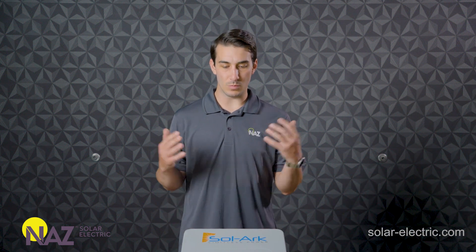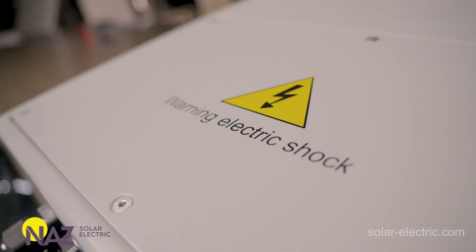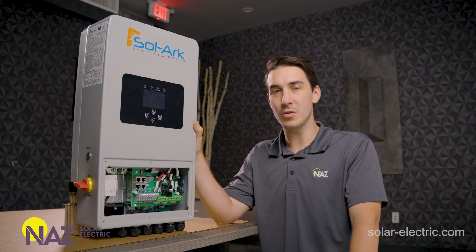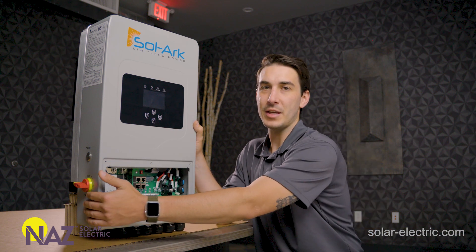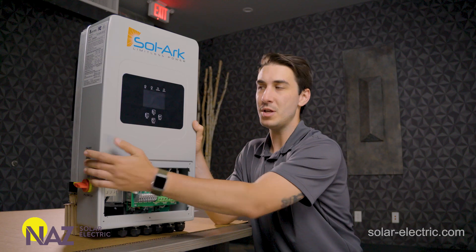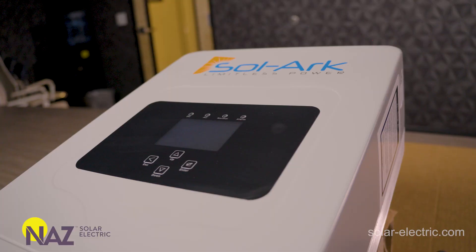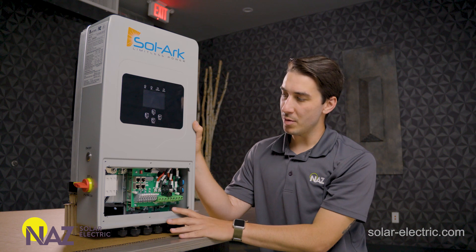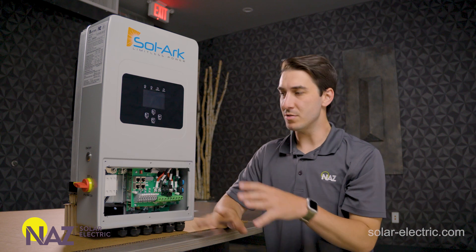Now that we've got a better idea of what the Sol-Ark 5K is, what it can do, and what kind of applications we can use it for, we're going to go ahead and take the cover off of the wiring compartment and take a look at the inside. We have the inverter propped upright on the table to take a closer look at some of the physical features and components. Starting on the exterior wall, we have our PV disconnect switch and then the off/on power button for the unit. Right in front, just like the other Sol-Ark models, we've got our touchscreen user interface, and then moving downward towards the wiring compartment — pretty similar layout to the other Sol-Ark models, but much more condensed with less going on in here.